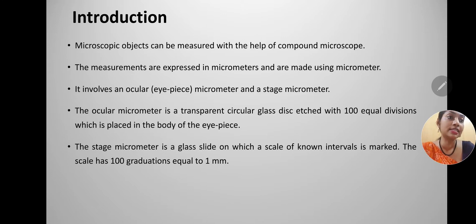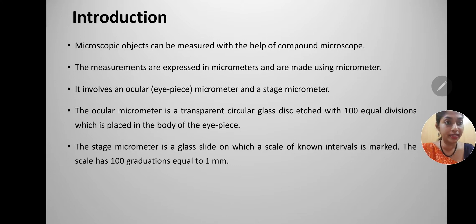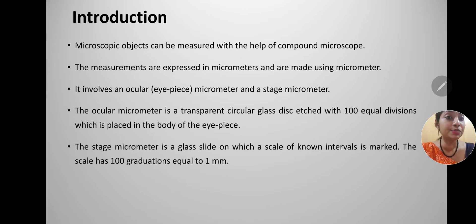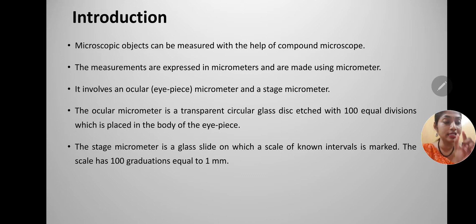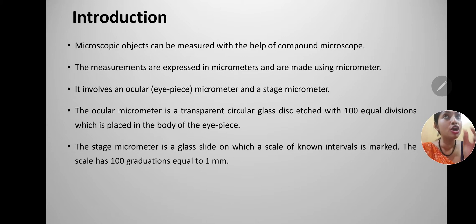An ocular micrometer is a transparent circular glass disc etched with 100 equal divisions, placed in the body of the eyepiece, and is therefore also known as an eyepiece micrometer. The stage micrometer is a glass slide on which a scale of known intervals is marked. The scale has 100 gradations equal to 1 mm, so each division is 0.01 mm or 10 microns.